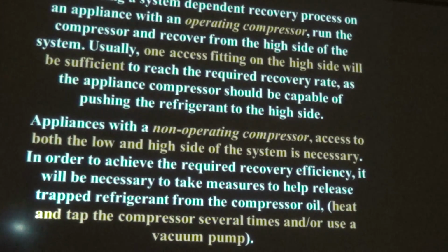However, if you have a type 1 appliance that has less than 5 pounds of refrigerant with a non-working, non-operating compressor, you will have to access both the low and the high side of the system. And you're going to access this with piercing valves. It would be necessary to take measures to help release trapped refrigerant from the compressor oil. Because there's going to be a little bit of refrigerant that's going to stay in the oil, you're going to have to heat and tap the compressor to get it out of the oil.